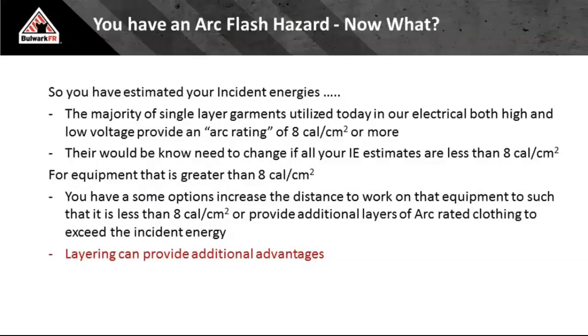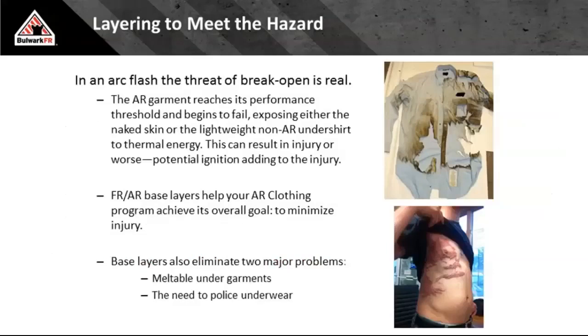Now, we do know there are cases when you might have 80, 90% of your equipment under 8 calories, and then you're going to have those few pieces of equipment that are outside the norm. They may be 12, 20, 30, 40, depending on what the gear is, MCCs, all those things. What can we do there? We can look at layering as an option, before we have to climb into the appropriate arc flash suit. So what does layering provide us with? Well, first and foremost, remember I said that second layer of protection?